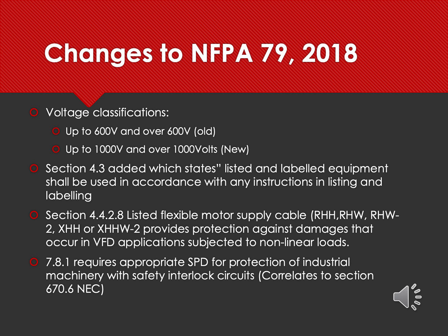This is an exact alignment with the NFPA 70E and 70B standards as published in the 2018 and 2019 editions. The next bullet addresses special cable requirements for flexible motor supply that protect the cables against damage in non-linear load applications. Primarily this is for variable frequency drives, to overcome damage to the cable itself. This is called out in 4.4.2.8, which is a new requirement too. And the last one is 7.8.1, which requires surge protection devices, or SPDs, for safety interlock circuits. These are some of the changes that came into play in the 2018 revision cycle. Let's go to the next slide.